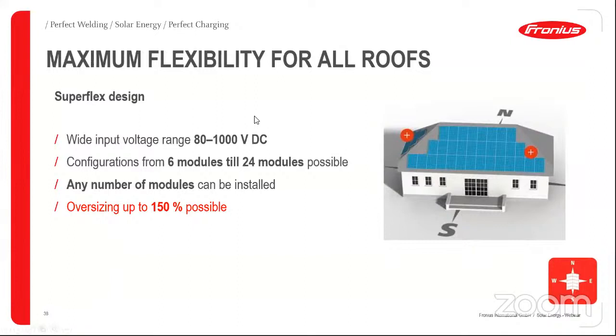Good. Another nice characteristic about Fronius is the flexibility we have to connect different modules to inverters. It's not needed to connect an equal number of modules in every MPPT of the inverter. We can connect a few in one of those and a different amount in the second one. And another very important characteristic, we can oversize the inverter up to 150%. What it means is we can, for example, have an inverter with 10 kilowatts, and on the DC side we can connect 15 kilowatts, with the intention to collect the maximum amount of energy during the operation of the inverter. We also know the modules have degradation, but we stay on the safe side using this oversizing in the inverter. It's allowed up to 150% without losing warranty, without losing the lifetime of the inverter.